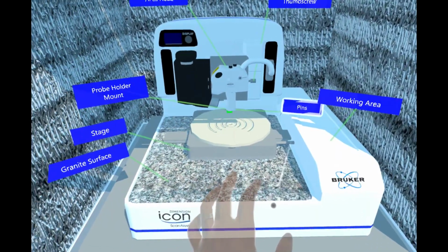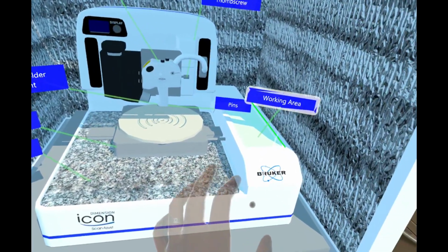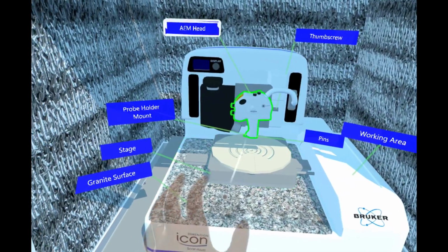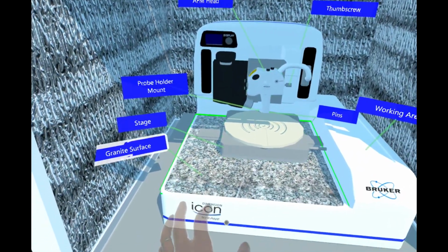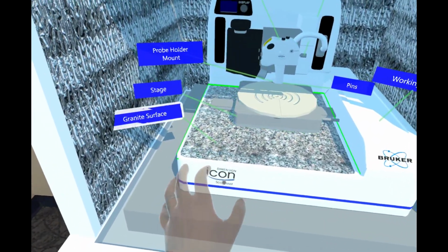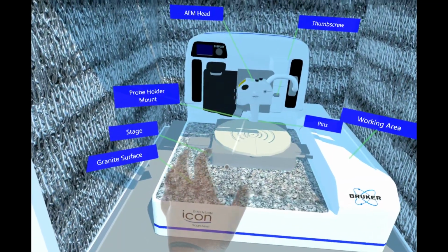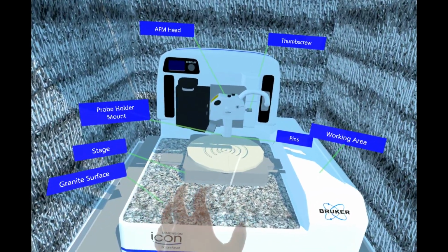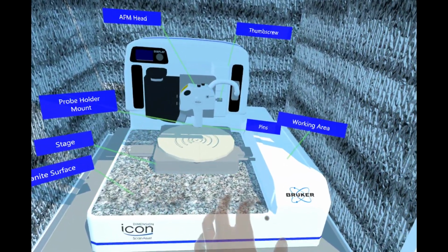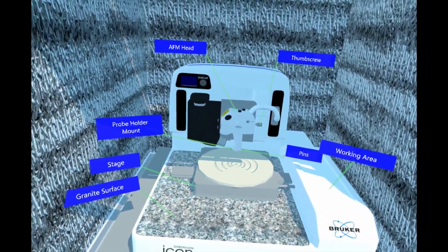The AFM head is one of the most delicate and expensive components of the AFM. A common way it gets broken is by dropping it or not paying attention to the brass pins on the end of the scanner and hitting them into anything. The handle makes it harder to drop, but it is up to the user to pay attention and protect the AFM head while it is in their hands.